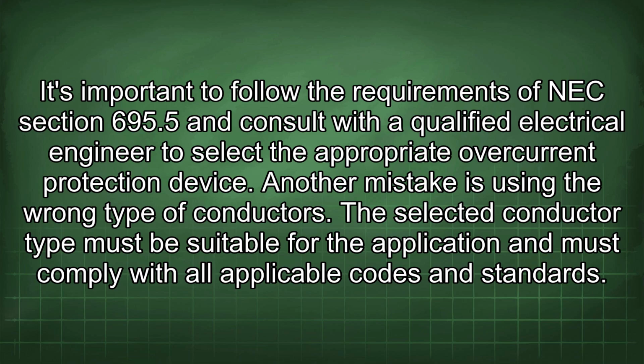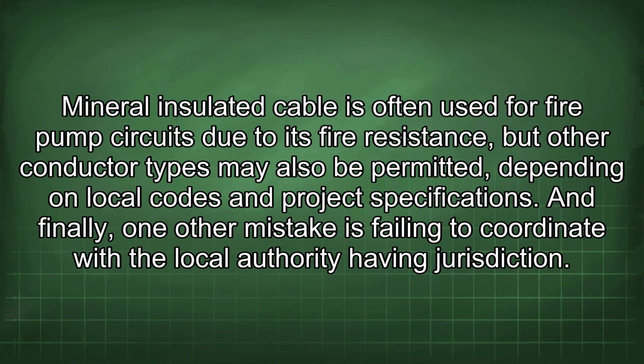Another mistake is using the wrong type of conductors. The selected conductor type must be suitable for the application and must comply with all applicable codes and standards. Mineral insulated cable is often used for fire pump circuits due to its fire resistance, but other conductor types may also be permitted, depending on local codes and project specifications.